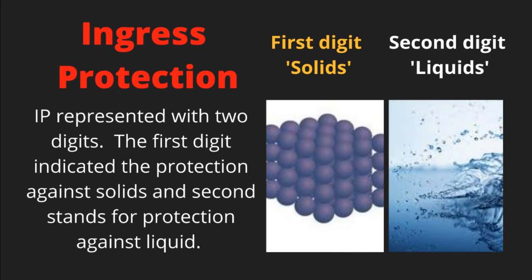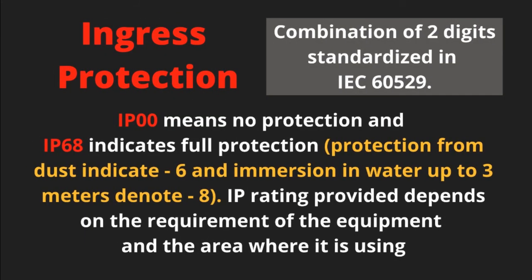Ingress Protection (IP) is indicated with two digits. The first digit indicates protection against solids and the second stands for protection against liquids. The combination of two digits is standardized in IEC 60529.